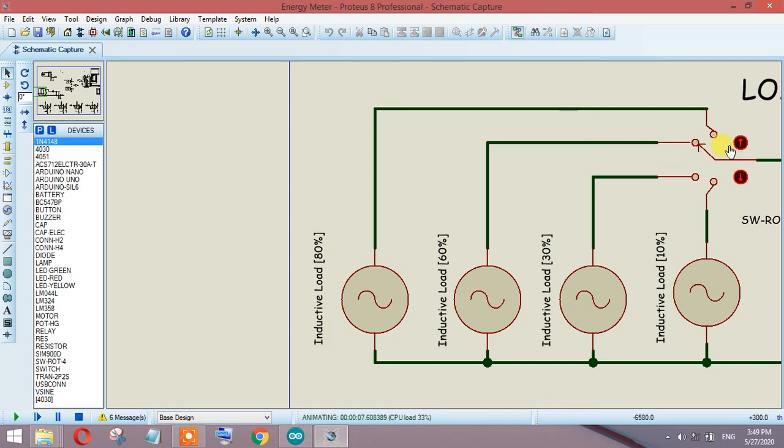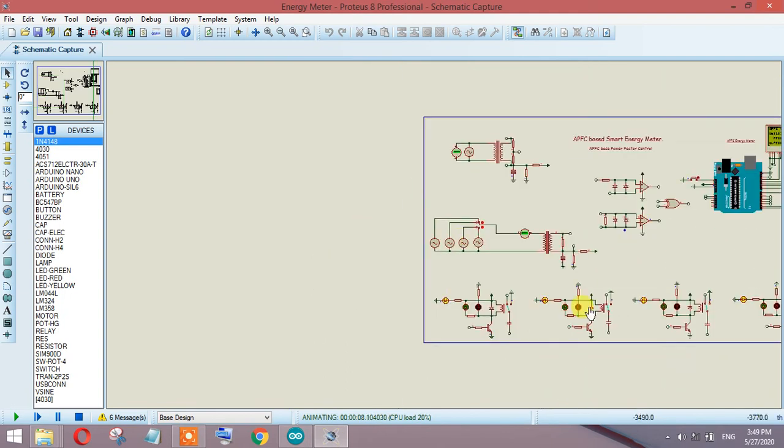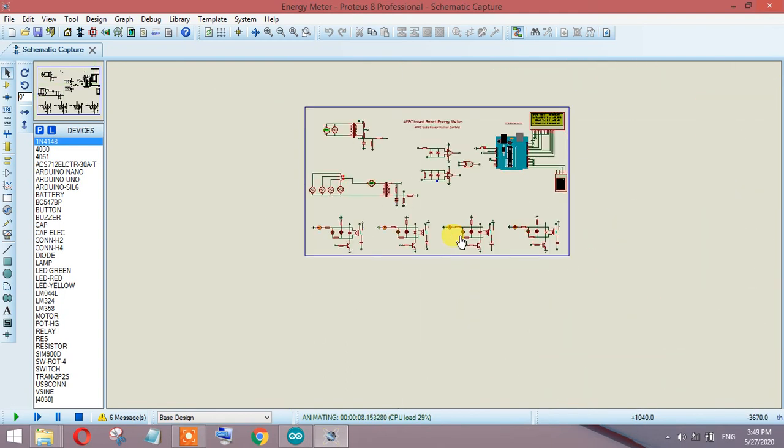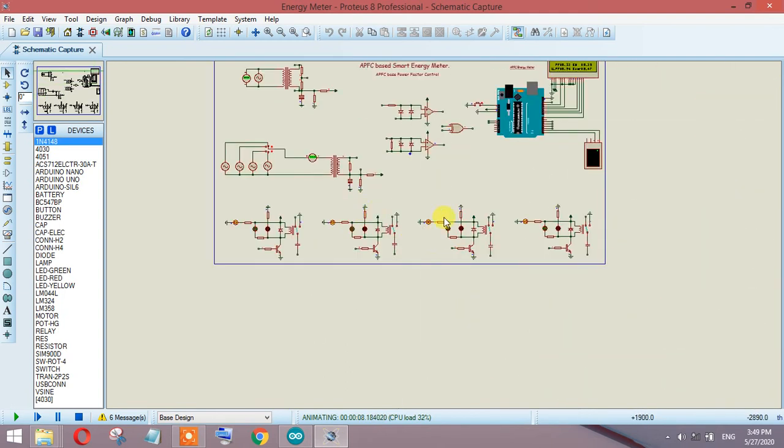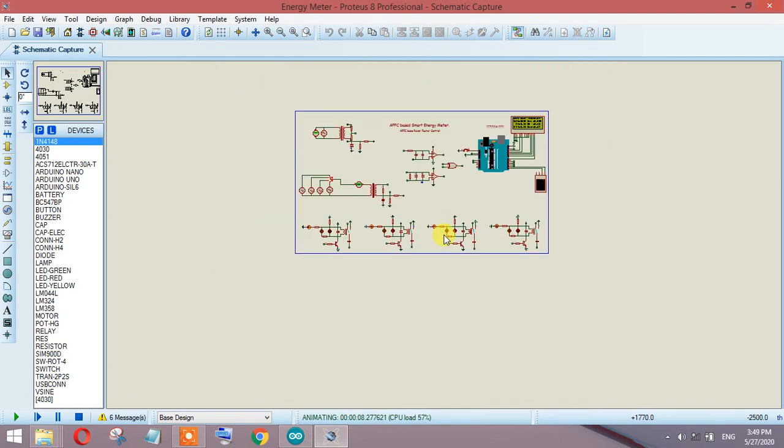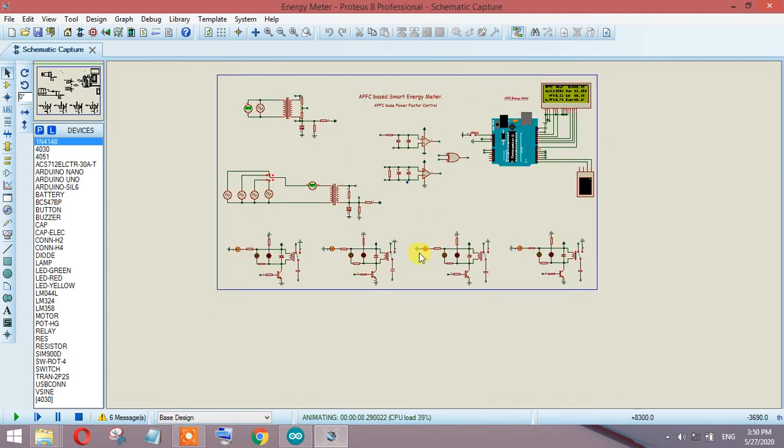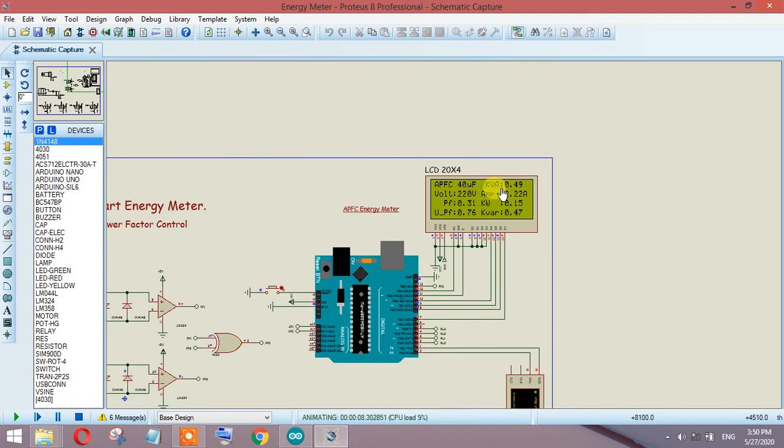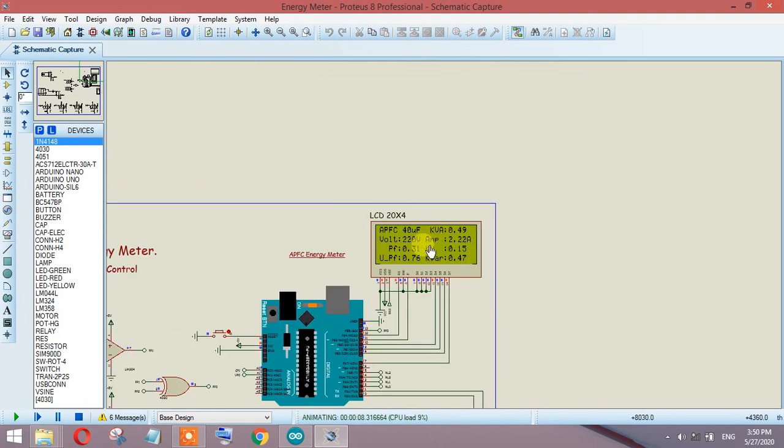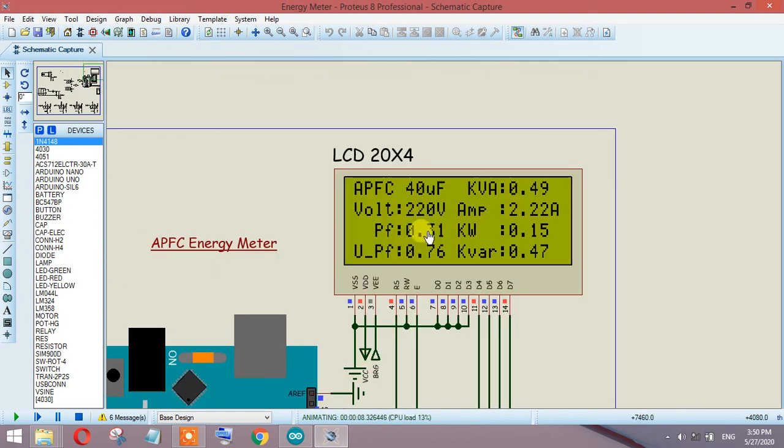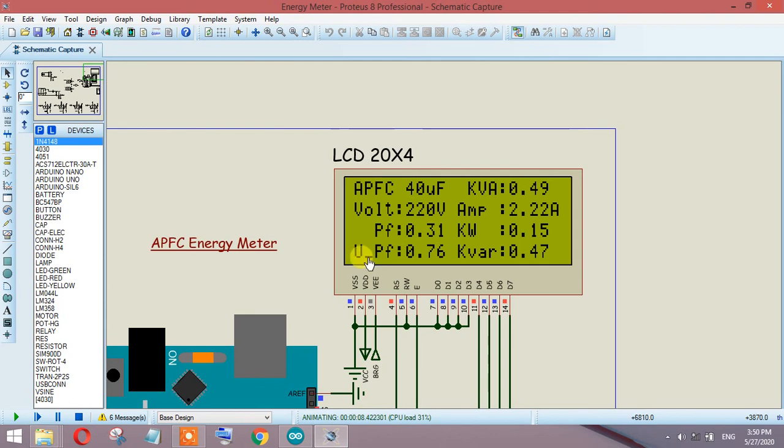Let's do one more thing and make it 80% inductive, the last stage. You can make many different stages but this is just to demonstrate. You can add a set of six, five, or four capacitors similar to this. Now the power factor dropped to 0.31, the updated power factor is 0.76. This is low but you can make it higher by using more capacitors.